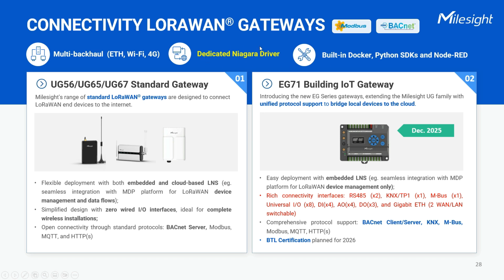A key feature for integration is our Niagara driver. Now, our initial integration was basic. You'd add devices on the gateway, map them as BACnet objects, and then push that data into the Niagara platform via BACnet IP. It worked, but it required you to manage both systems.